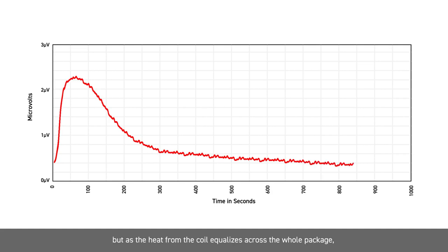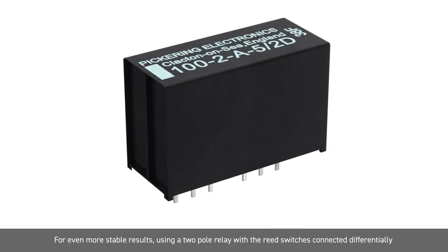The thermal EMF generated by the relay alone will peak when the coil voltage is initially applied, but as the heat from the coil equalises across the whole package, the resulting thermal gradient can see it stabilise at a lower level.